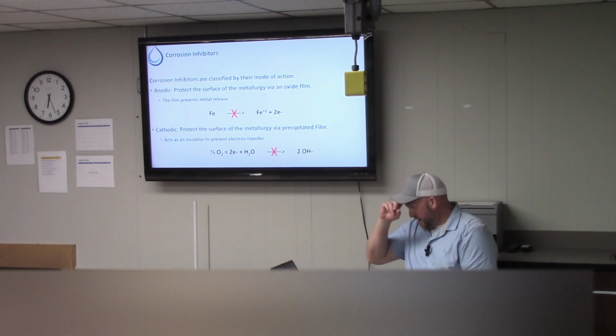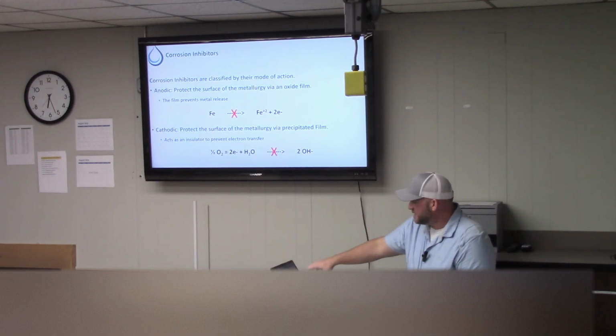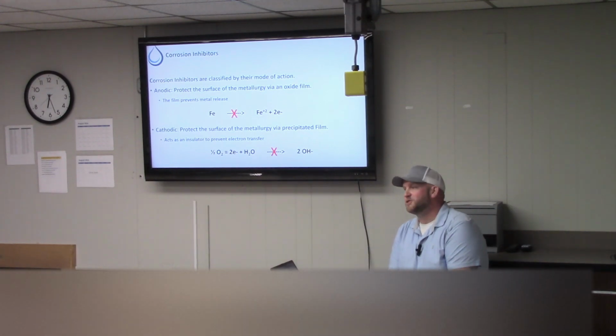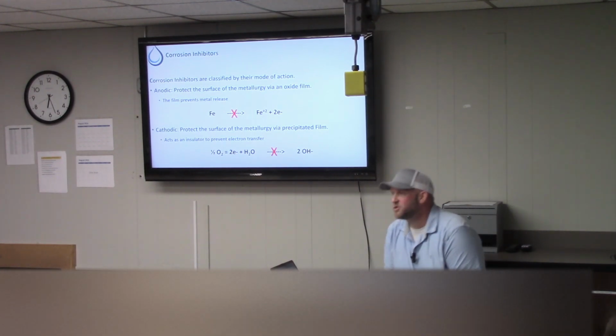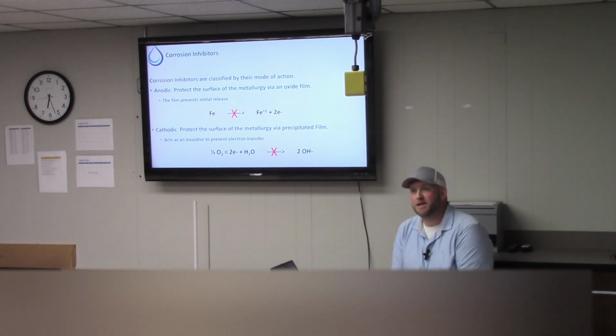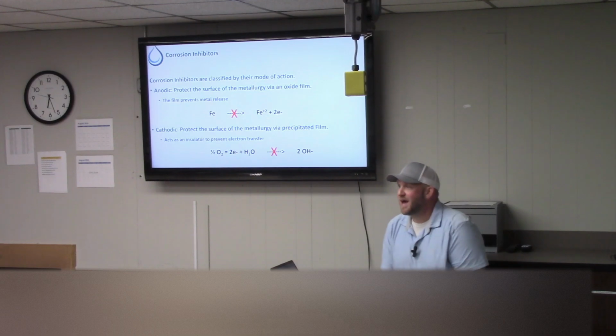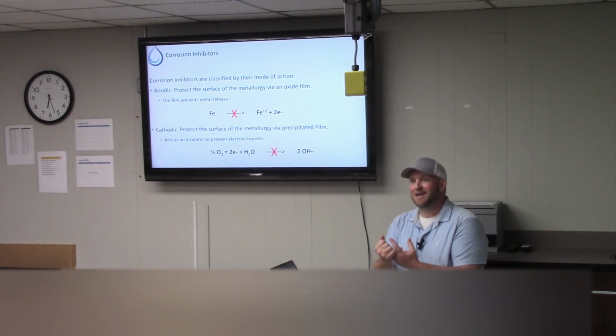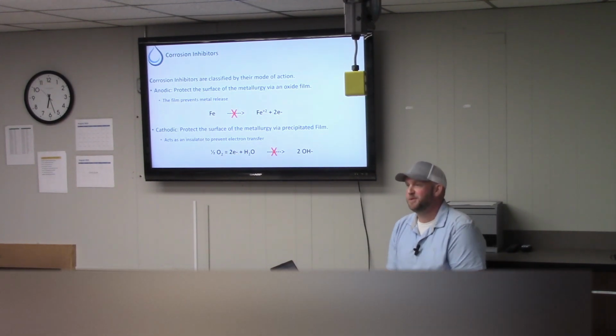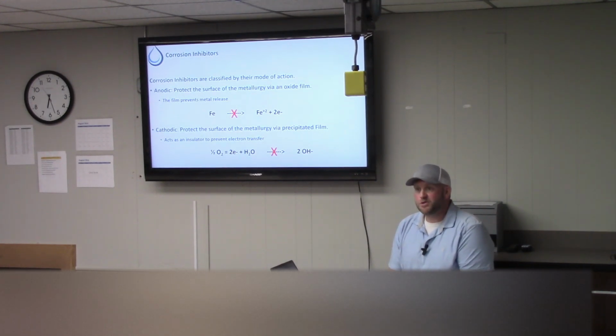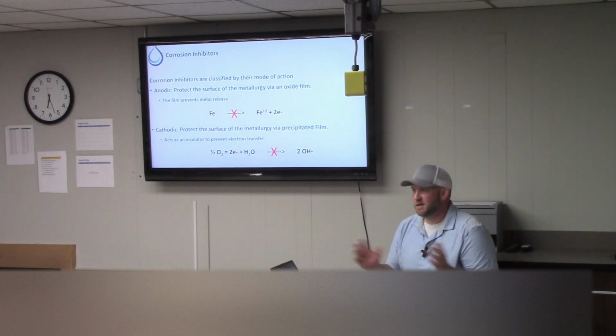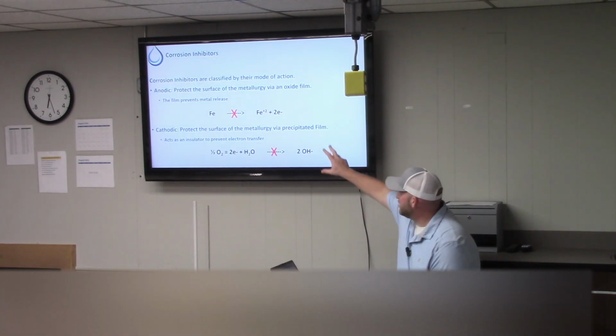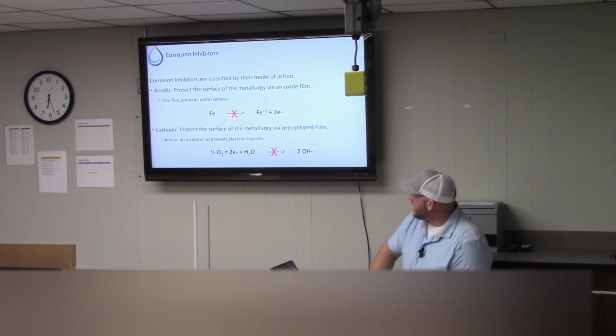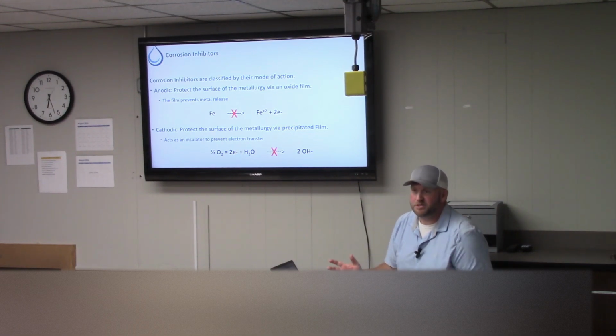When you look at that, what you find is phosphate was the thing the industry went to. So in a lot of your cooling tower chemistries out there, you're going to have phosphate as the main corrosion inhibitor. It was economical and it had anodic and cathodic corrosion inhibition properties. For those of you that like to geek out in chemistry, that's a 2-for-1 deal that is hard to pass up. When you can inhibit both of those and walk away with one bill, that's just smart.